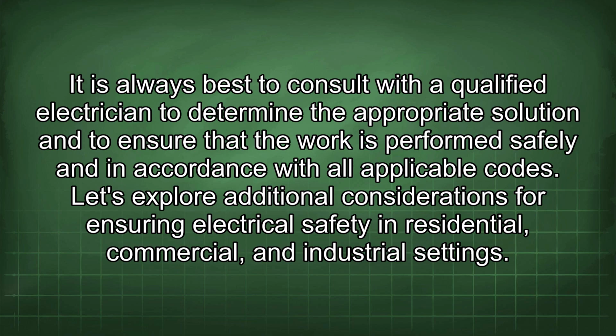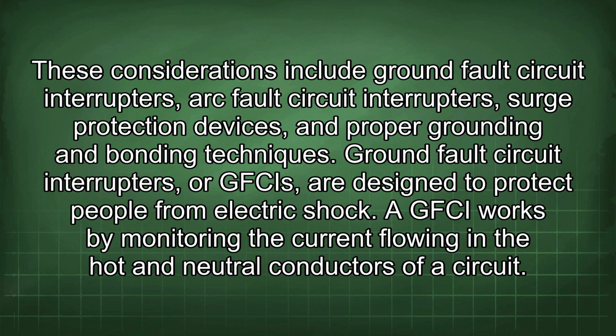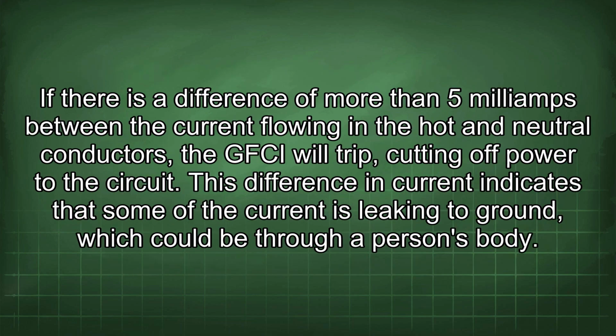Let's explore additional considerations for ensuring electrical safety in residential, commercial, and industrial settings. These considerations include ground fault circuit interrupters, arc fault circuit interrupters, surge protection devices, and proper grounding and bonding techniques. Ground fault circuit interrupters, or GFCIs, are designed to protect people from electric shock. A GFCI works by monitoring the current flowing in the hot and neutral conductors of a circuit. If there is a difference of more than 5 mA between the current flowing in hot and neutral conductors, the GFCI will trip, cutting off power to the circuit.